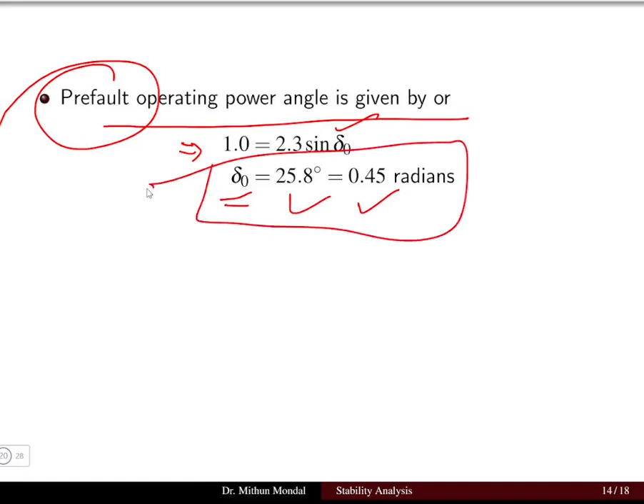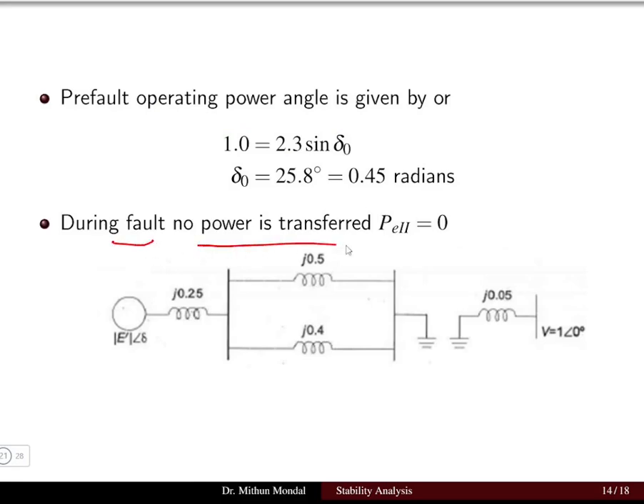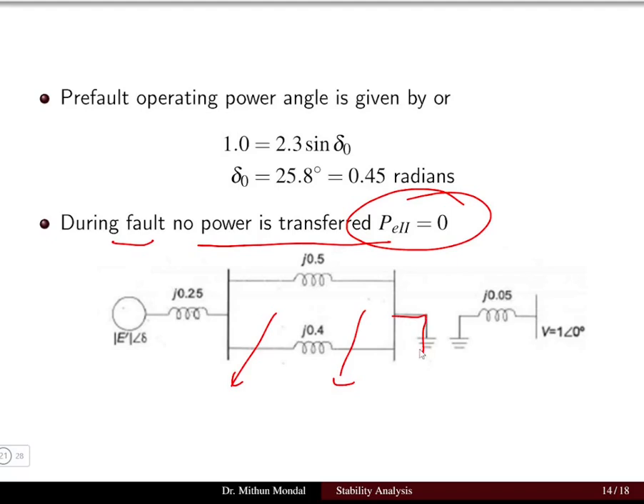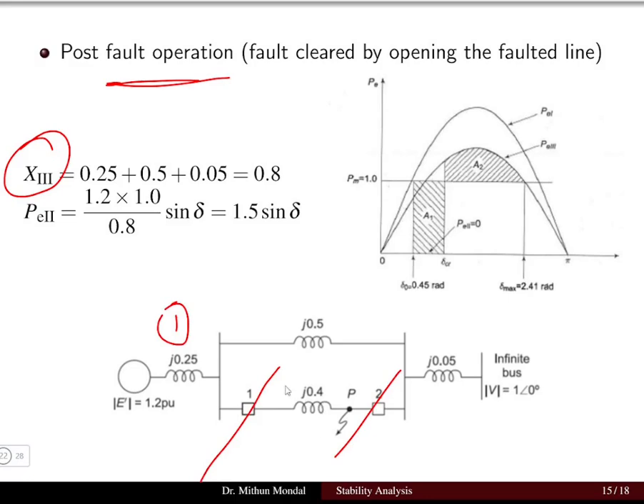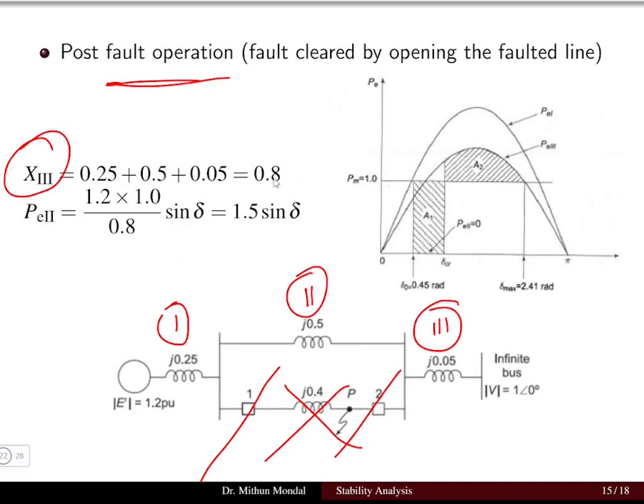During the fault, no power is transferred to the system, so Pe = 0. In the post-fault condition, breakers 1 and 2 have opened, disconnecting one line. The remaining path has reactances j0.25 + j0.5 + j0.05 = j0.8 per unit total.